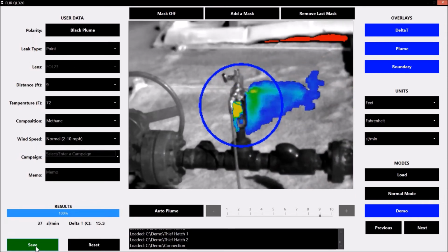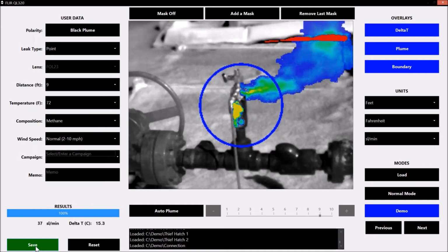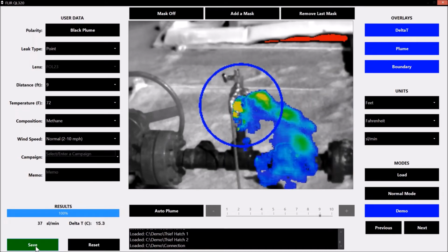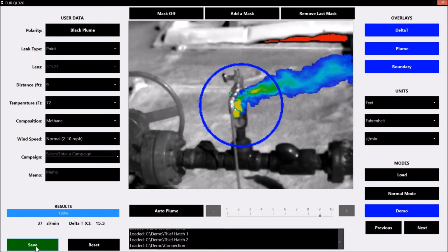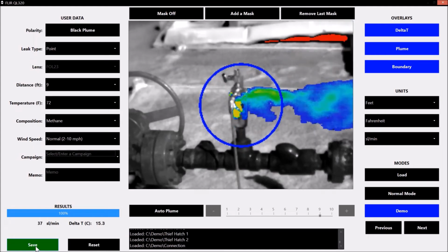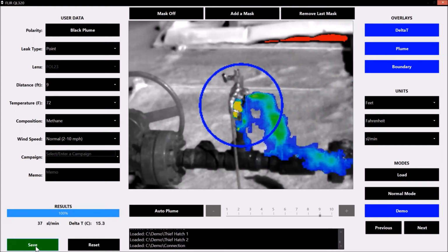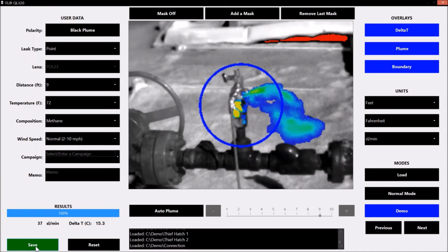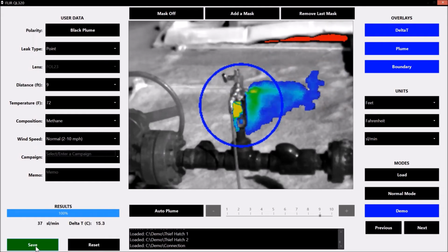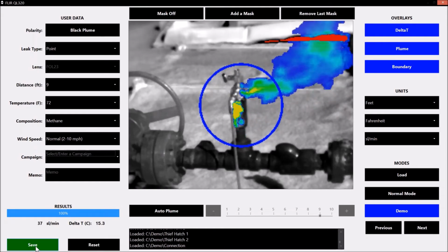There are some competitors that, when you start looking at specifications, may not claim what delta T they use when they're providing minimum laboratory limits of their technology. If they use 20 delta T, they could actually very much skew it, because it's not always that you're going to have a 20 degree delta T in your environment.